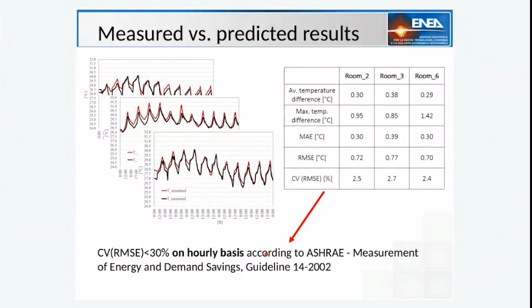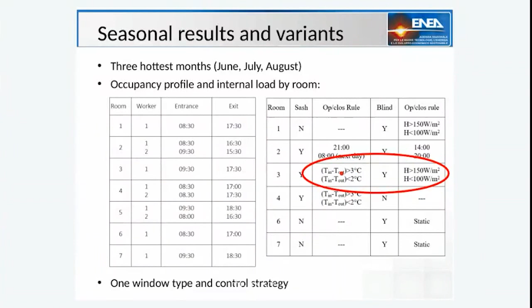Once we calibrated the model, to make the seasonal variation we needed to make some simplification and also some standardization. As an example, for the occupancy on the longer term, we made interviews with the occupants to try to understand their typical office hours, so how many workers in each room and what was their typical occupancy pattern. Then we implemented a single strategy for the night ventilation with the windows opening and the solar shading activation.